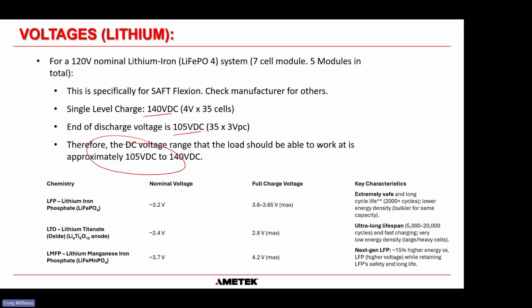And that's exactly what the lithium ion manufacturers are trying to do. They're trying to replicate lead acid batteries so they can be used in an industrial setting. But do bear in mind, there are many, many different chemistries. So for an LFP, which is lithium iron phosphate, the nominal voltage is 3.2 volts per cell and full charge here, this is actually incorrect. I pulled this table from one particular manufacturer. This can be 4 volts per cell. And that just shows how confusing data can be on the internet sometimes.